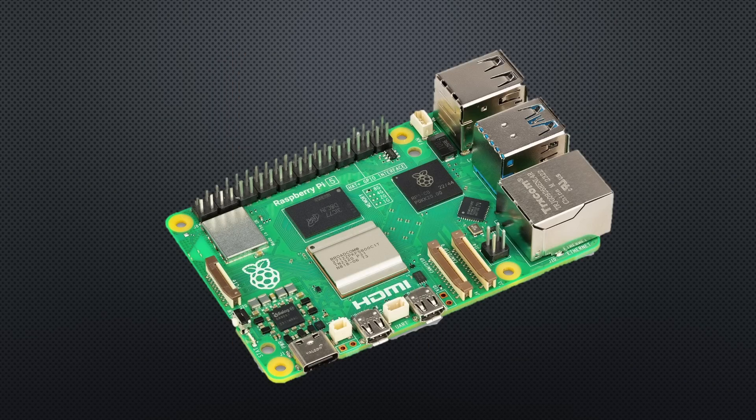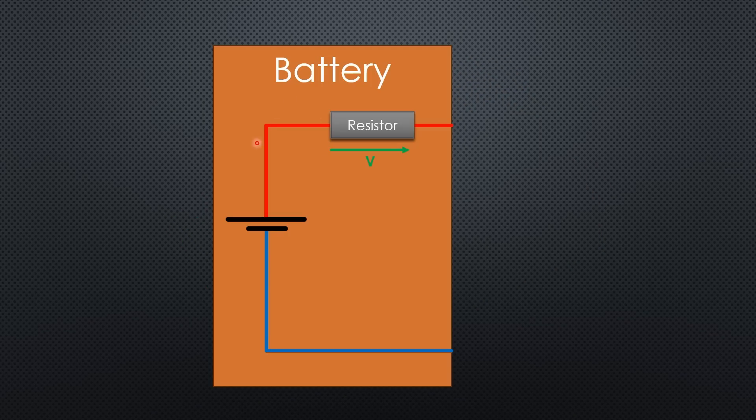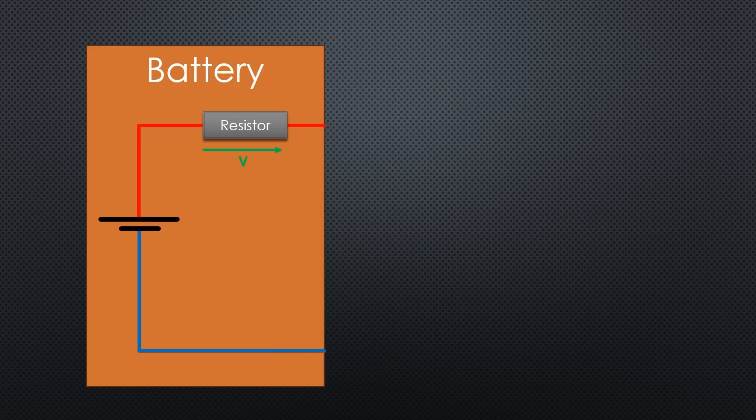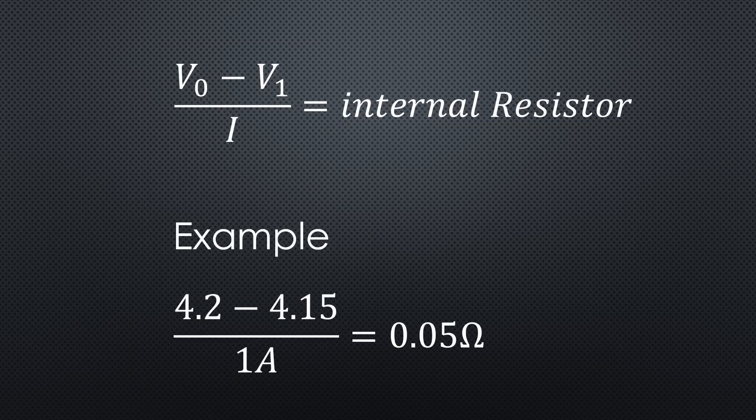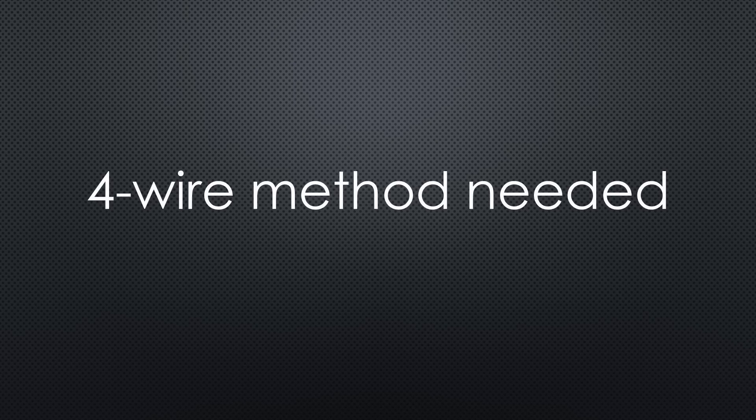Because this internal resistor has no legs, it is hard to measure. And we have to use a trick. First, measure the voltage without current. Then, apply a load to draw current and measure the voltage drop. Use Ohm's law to calculate resistance. The internal resistance varies with the battery's state of charge, discharging current and temperature. Since these resistances are small, the 4-wire method is necessary for accuracy.